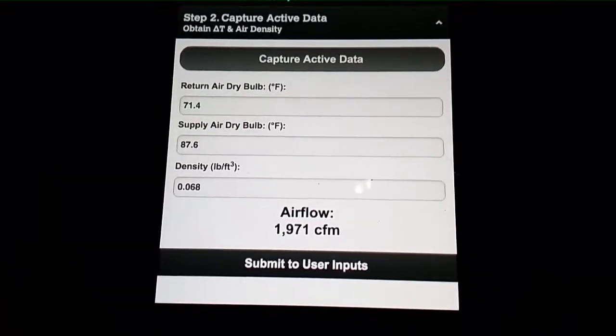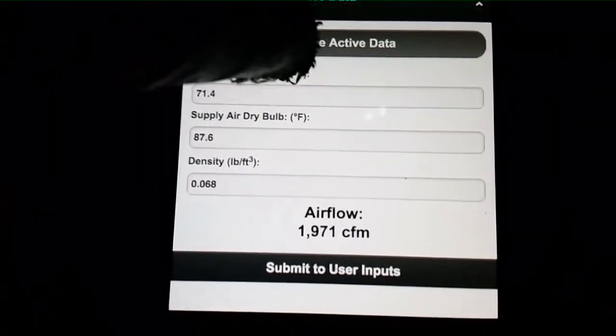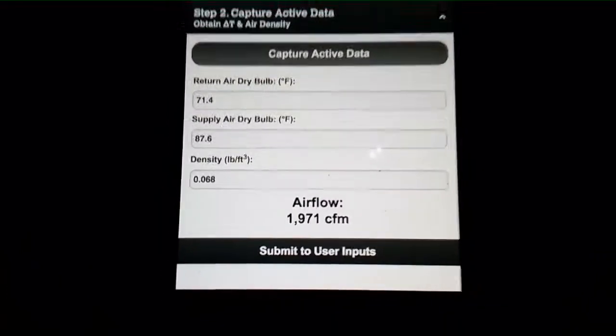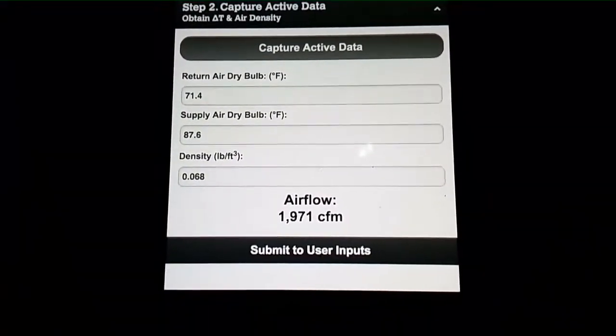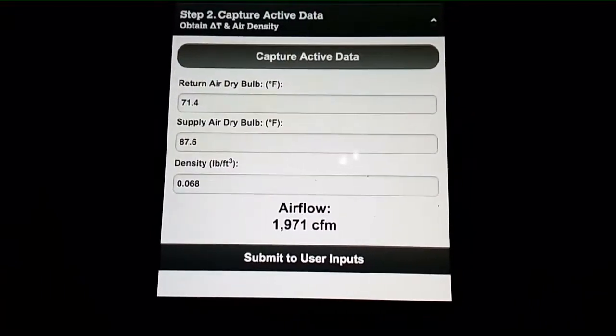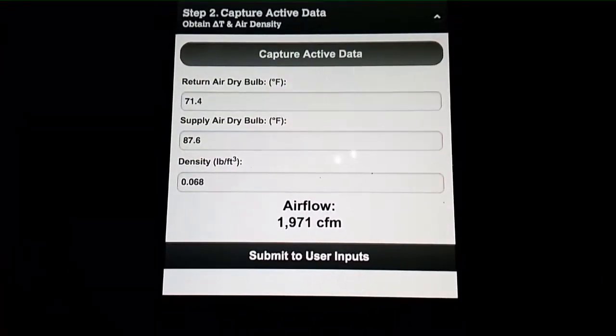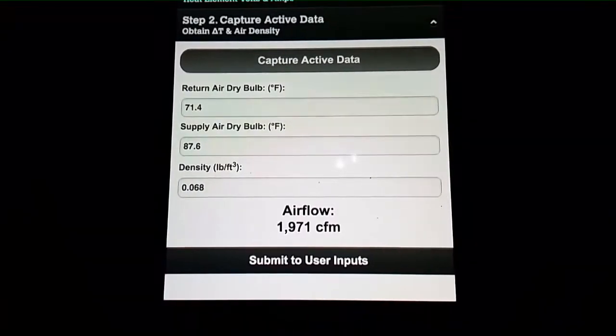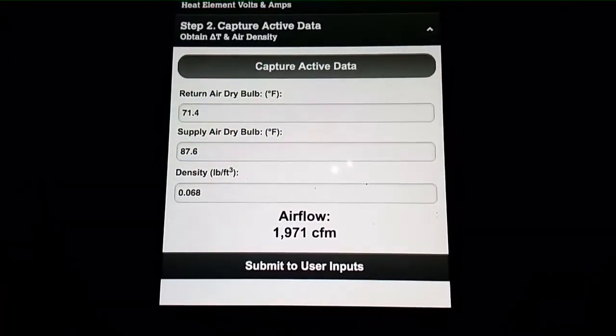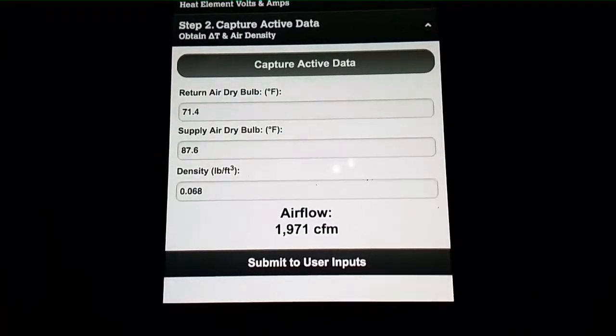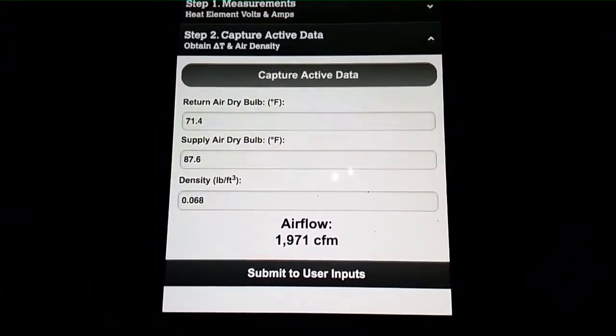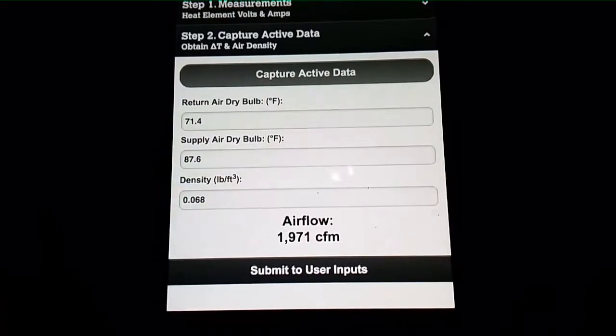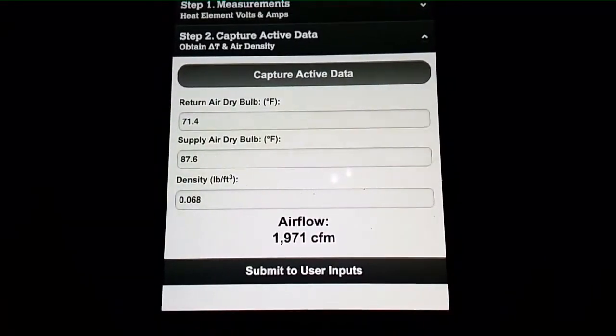Right now we're doing around 1971 CFM, so a good amount of airflow. Again, it's the highest amount of airflow we're going to use because we have a heat pump running in heat with auxiliary running, so it's going to be the most airflow it uses because it's going to be moving a lot of heat with both of those items going, the compressor and the strips themselves, because there's 10 kW there. 10 kW, you're looking at about 3 tons worth of heating, 36,000 BTUs or so nominal. A little bit less than that, but the idea is a lot of heat moving through there. Counting the 4 tons of heat, think of it as like 7 tons, to put it very simply.